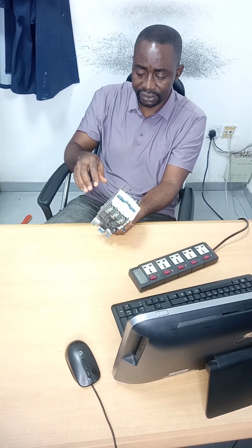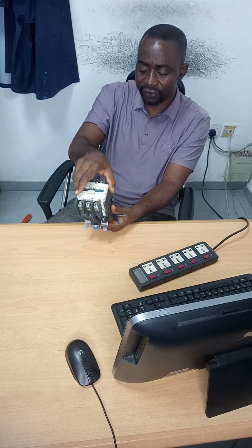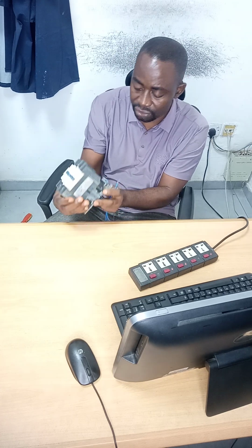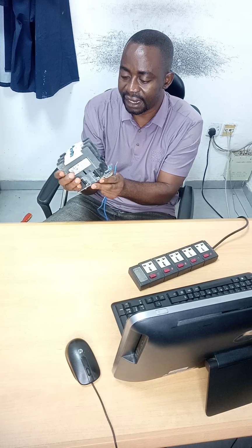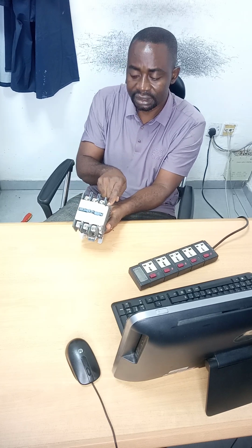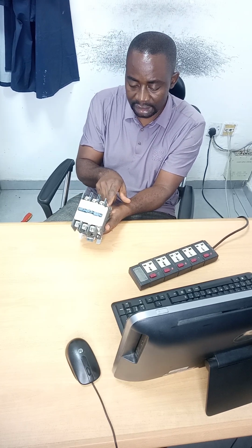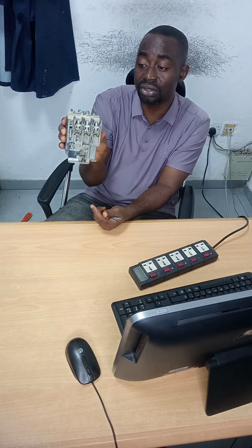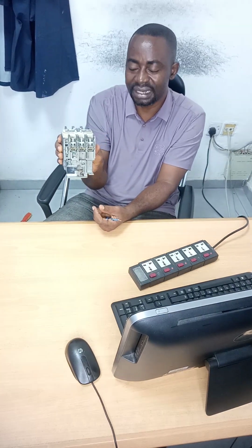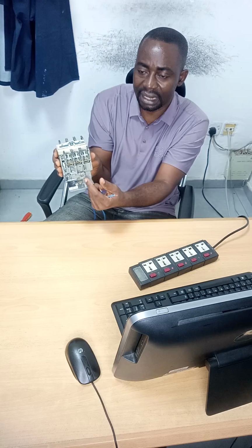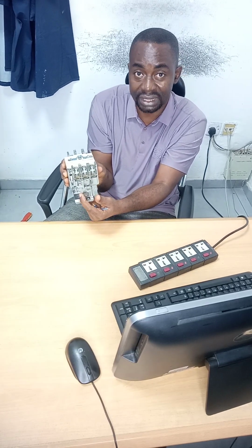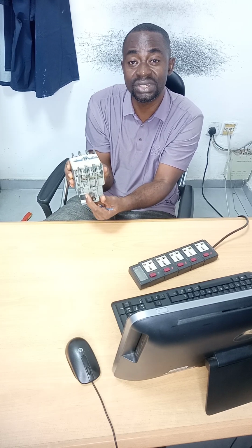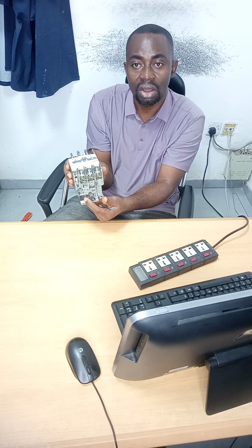Now, what you look out for is where you can see A1 and A2. Like I can't see it from this side. I check. Okay, yes, this is A1 and A2. That is here right now. Yes, the contactor is usually a three-phase contactor, but it is designed in such a way that the A1 and A2 terminals can be used to test its functionality. So what that is telling you is that you use single phase to test the functionality of the contactor.